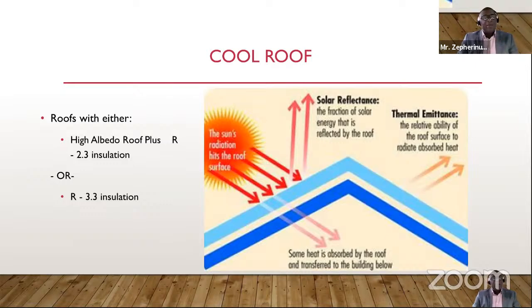In the absence of a high albedo roof with the resistance of 2.3, we now have the resistance, the R value, for insulation of that roof at 3.3. So you see an increase in the insulation if it is not a high albedo roof. So provisions for the roof, I mean, some of the architects will say to you that even the color of the roof, a white roof or light colored roof, would attract less heat than a black roof. And we see more and more construction in the region where people are beginning to use dark gray colors for roofs.